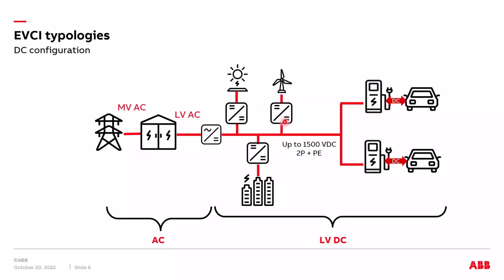And then we have locally the same generation, but now this local generation is connected by means of a single rectifier or a single DC-DC converter in order to adjust the local production with a fixed voltage to the rated voltage of our distribution line. And here, if we talk about a low voltage distribution system, so far the maximum voltage is up to 1500 volt. But here it is up to the designer to decide which could be the rated distribution voltage.